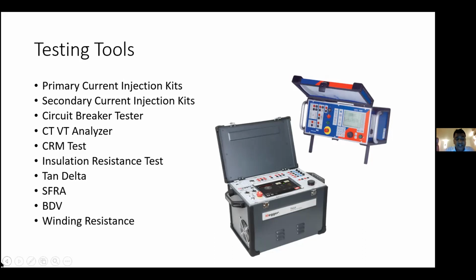Then there are circuit breaker analyzers, CT-VT analyzers, and CRM test kits—CRM being contact resistance measurement test. There's also insulation resistance test, tan delta to test the insulators of transformers, SFRA test to test the mechanical suitability of transformers, BDV test (breakdown voltage test) for transformer oil, and winding resistance test.